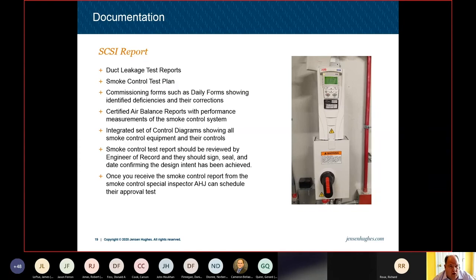But documentation is also a big part of this. There's a requirement to have a smoke control special inspection report, and that combines all the things during the design and construction phases, leading up through the testing, and puts it in one location. That report includes duct leakage tests, to see how leaky the ductwork is way at the beginning of the project.